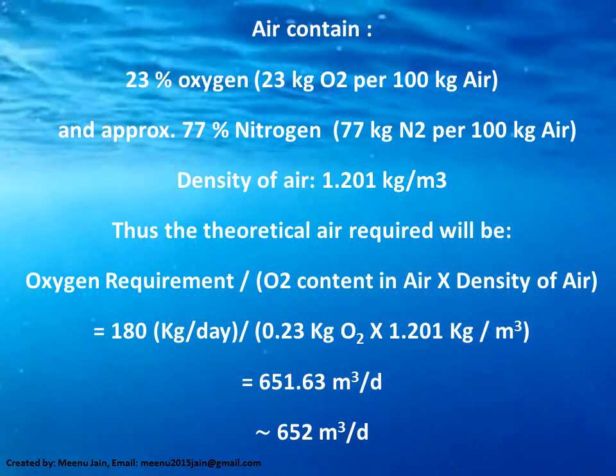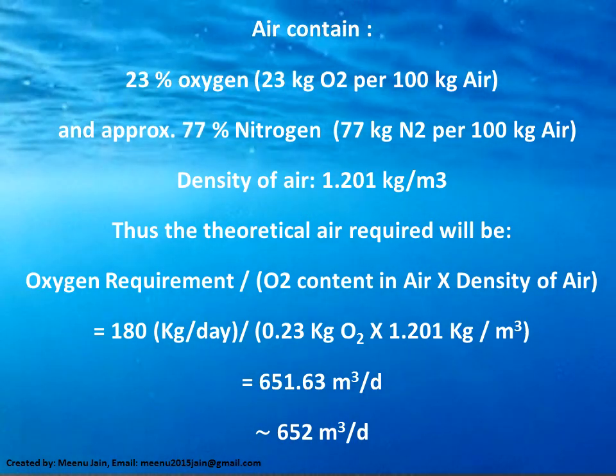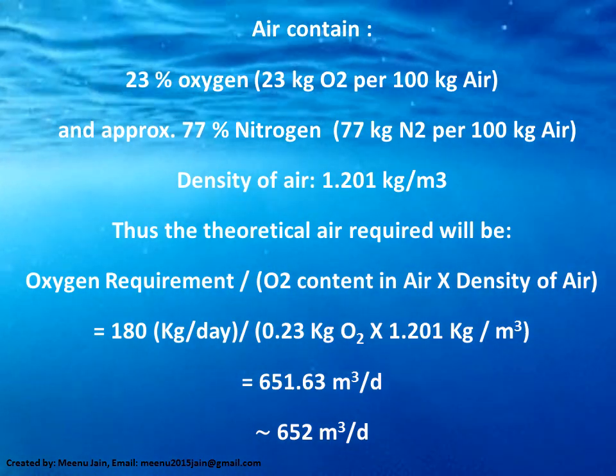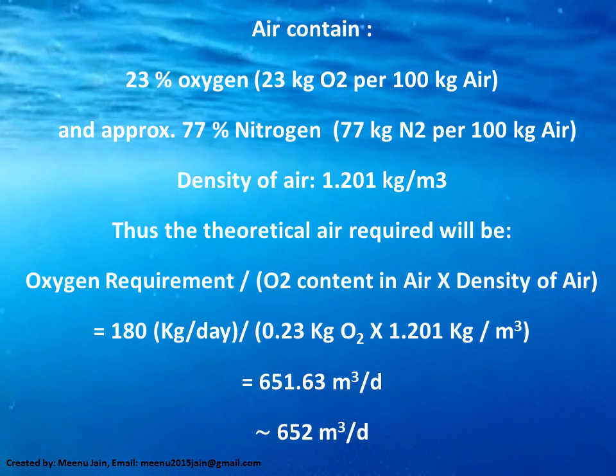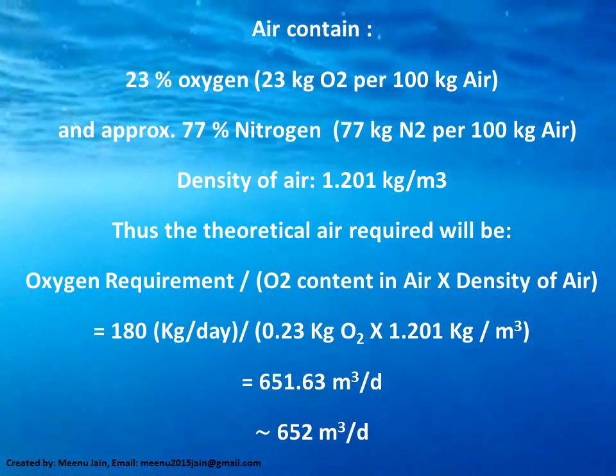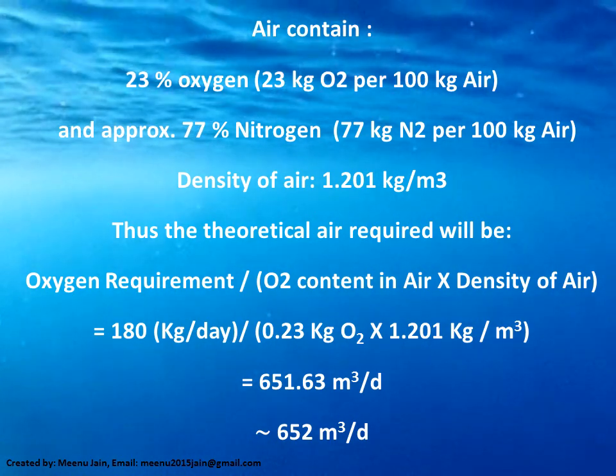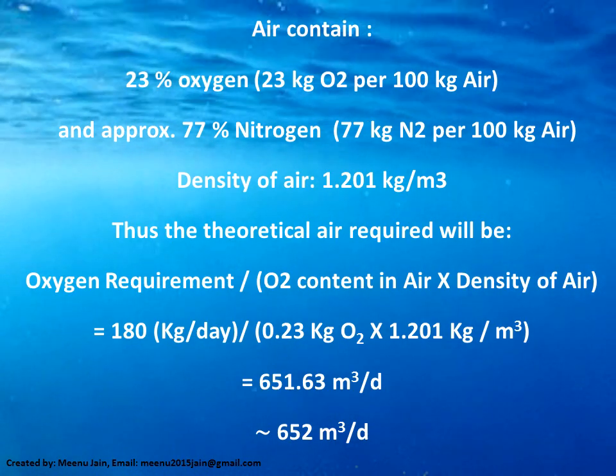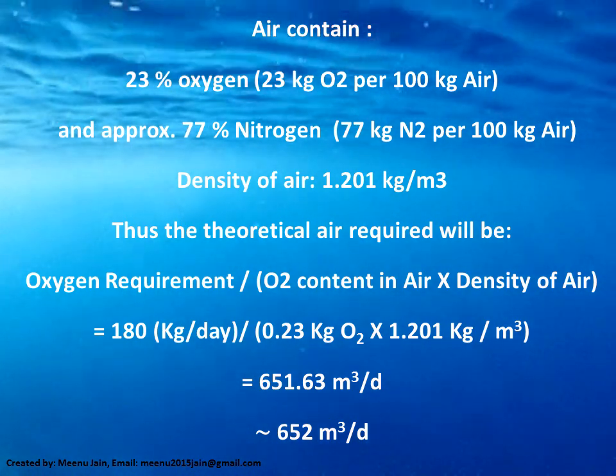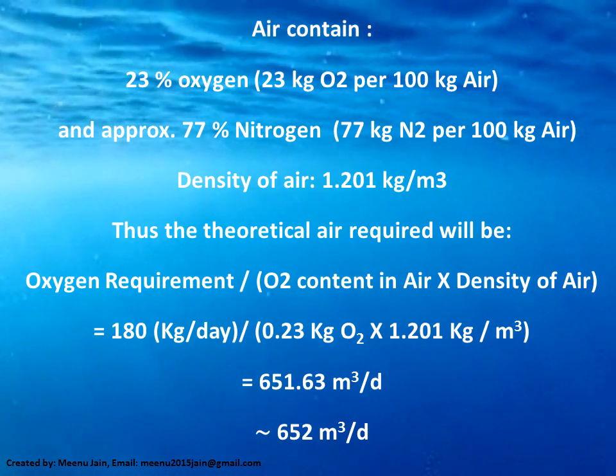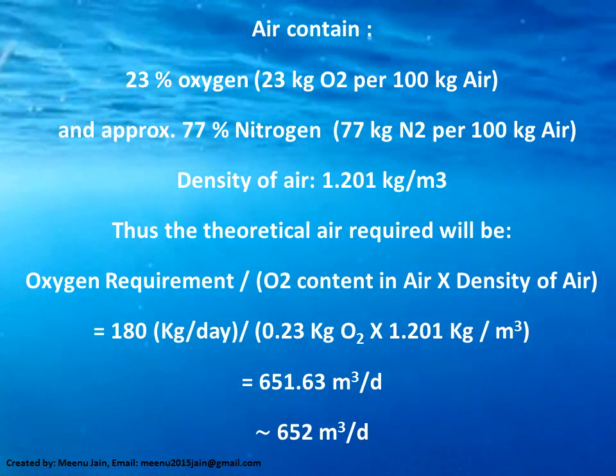Atmospheric air contains 23% oxygen (23 kg per 100 kg of air) and approximately 77% nitrogen, and the density of air is 1.201 kg/m³. The theoretical air required equals total oxygen requirement divided by O₂ content in air, divided by density of air: 180 kg/day ÷ 0.23 ÷ 1.201 kg/m³ = 651.63 m³/day, or approximately 652 m³/day. This is the air requirement for BOD removal in our MBBR tank.